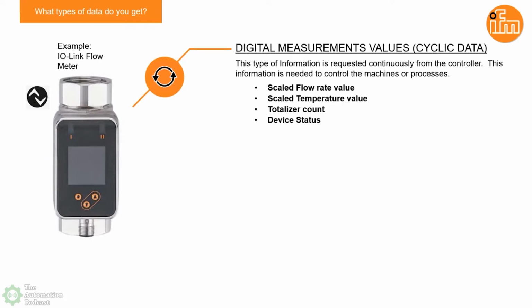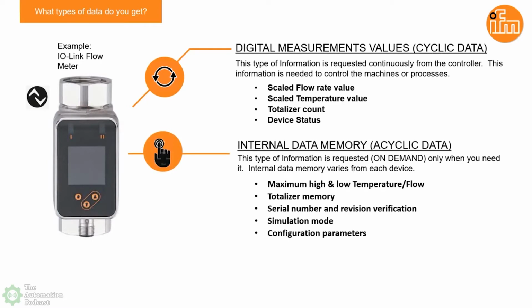In addition to that, you also have another segment of data set that you can get. We consider this the internal data memory of the sensor, and this is what we also refer to in IO-Link as acyclic data. I usually call this on-demand data, because it's not information you typically need to control the machine continuously. Maybe there's an event, maybe some information you want at certain times of the process, but you don't need it all the time at the PLC, because the PLC also has a certain amount of information it wants to take. You don't want to give it too much information—only give it information when needed, so you don't overload it.